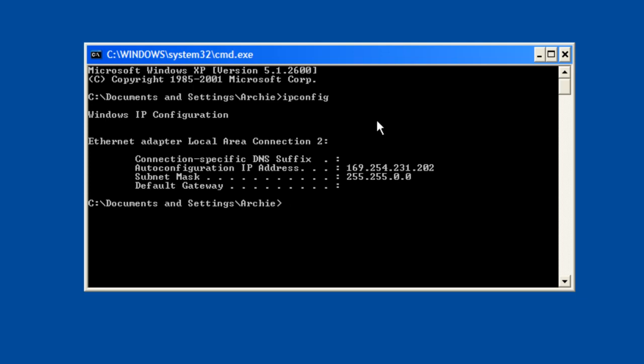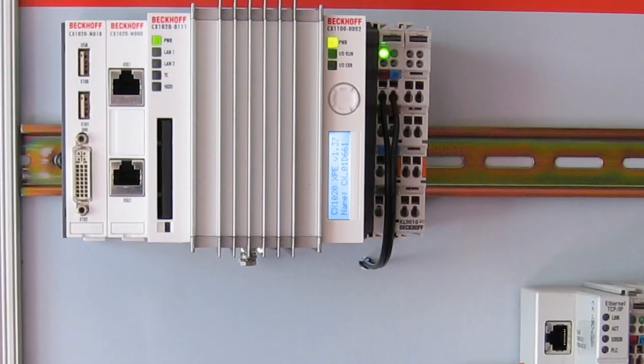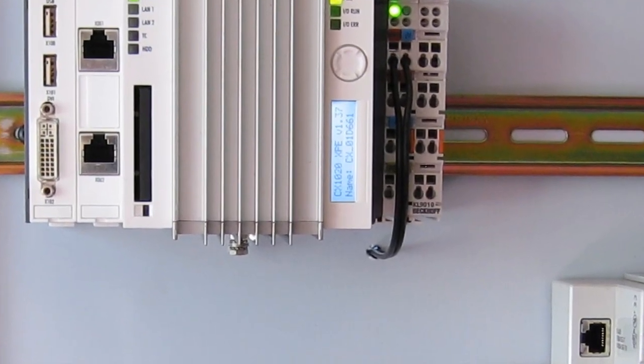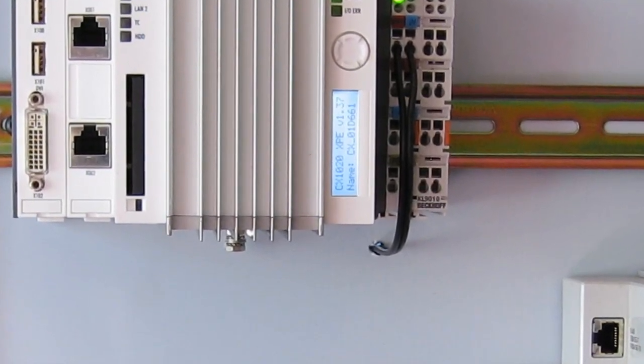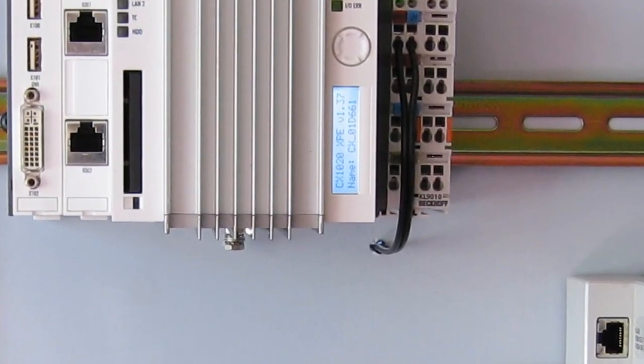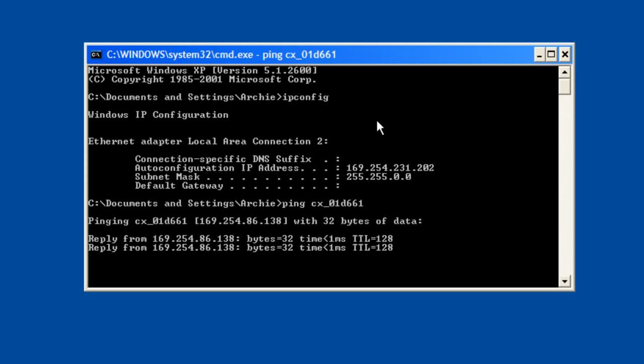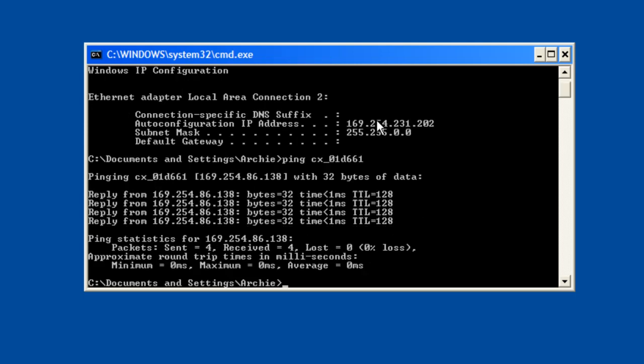So now let's do one other quick test. If you look on the screen of your CX processor, the little two line display, you will see the name of the controller and it is going to be a CX underscore and a few numbers. So let's type ping CX underscore and type in those numbers that you have seen on the two line display. And once we type that in we are going to press enter. Now what that will do is resolve that name to an IP address and you should see a response back from the controller. That validates that we have a successful connection.